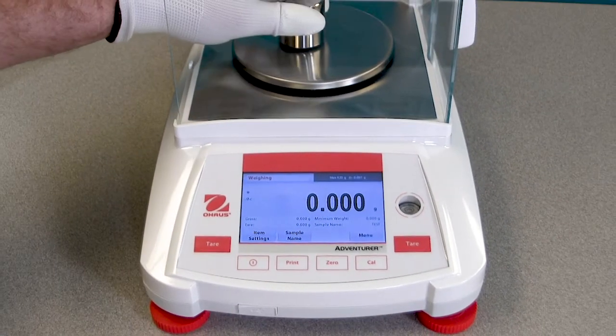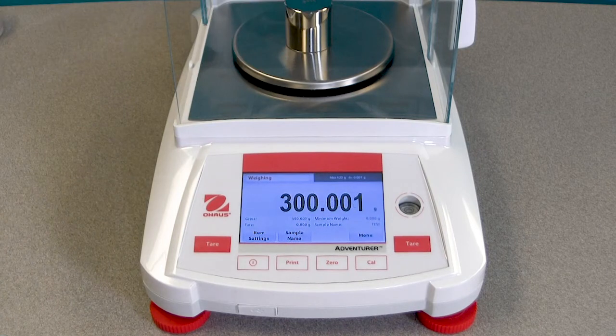After calibration, place the test mass on the pan and verify that the mass value now matches the displayed value. If not, repeat the procedure until the internal calibration reading agrees with the test mass. Once completed, the balance stores the adjustment value and the display returns to the current application.